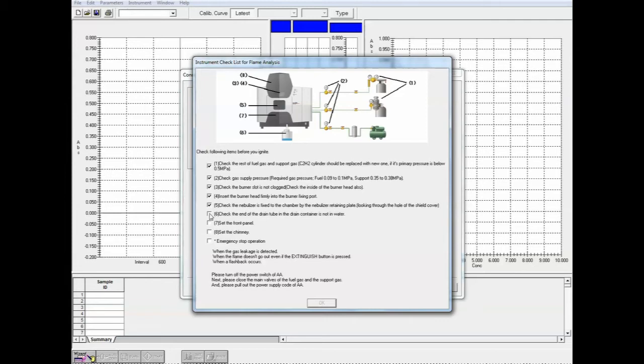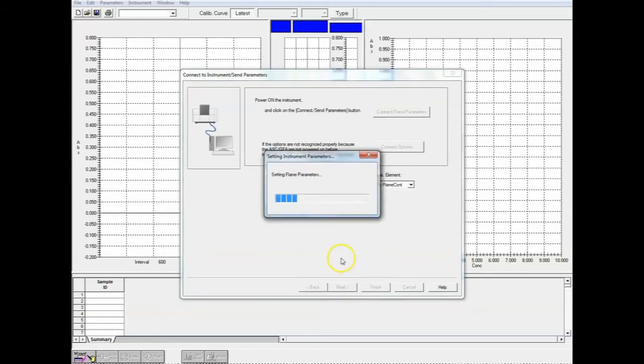Make sure the end of that drain tube is in the container, it's not in the water. So we want the drain tube to be above the surface of the water. That's that hazardous waste jug that I showed you. Making sure the front panel is on, so remember we had to take that off to check the drain sensor. Set the chimney, so that's the portion that covers the flame. And emergency stop. We'll check all of those things and then say OK. Now it's sending the information to the machine again, setting the parameters.